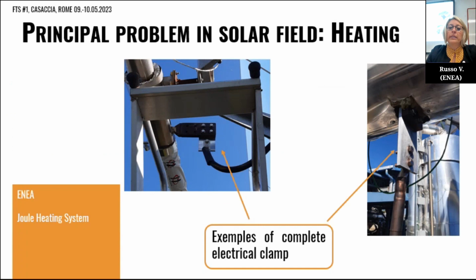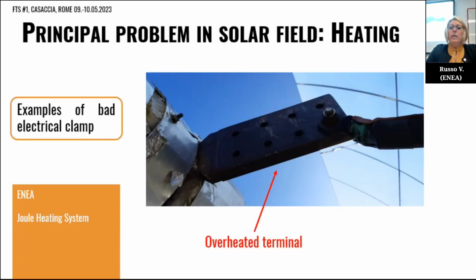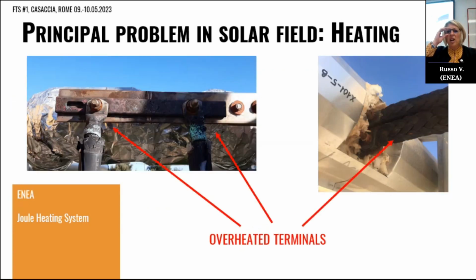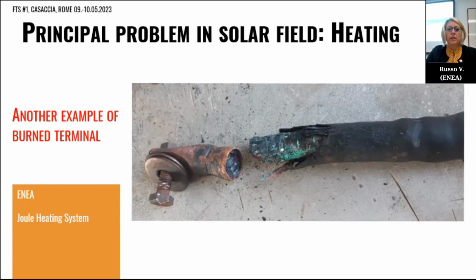Here we have some examples of installation of the electric clamp on the solar field. The correct way to install the electric clamp. If the electric clamps are not soldered in the right way, the aluminum plate can be overheated. And here we can see in fact a plate damaged from the overheating, perhaps because in this case there wasn't a good contact between the surfaces. Again, another example of overheated terminals. Here we can see the rubber sheets burned. And the last picture of an overheated cable that is broken.